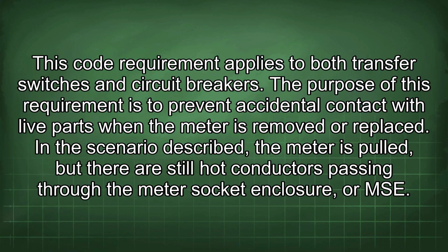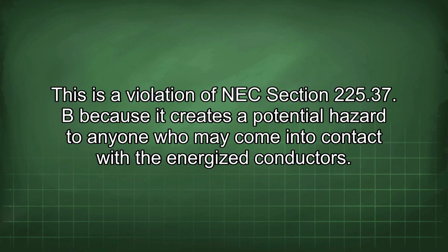In the scenario described, the meter is pulled, but there are still hot conductors passing through the meter socket enclosure. This is a violation of NEC Section 225.37(B), because it creates a potential hazard to anyone who may come into contact with the energized conductors.